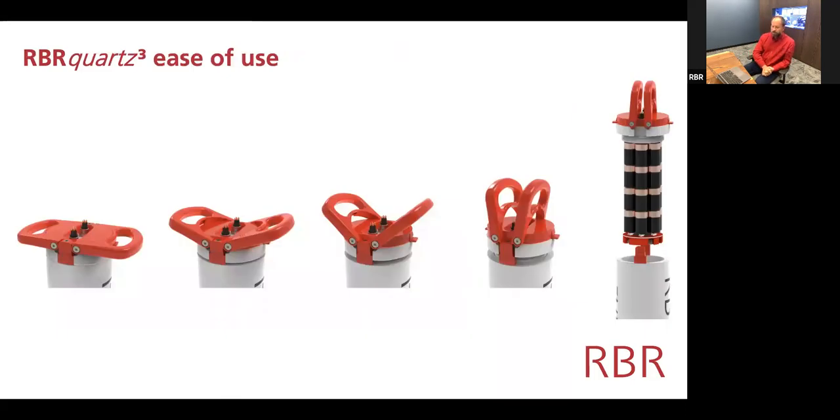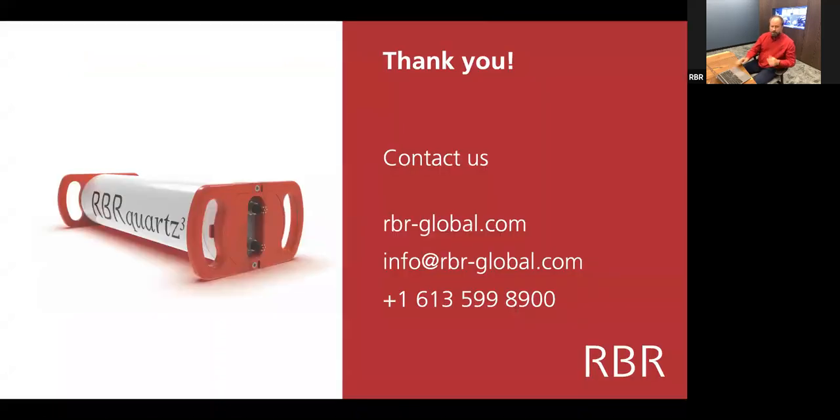We don't ship RBR instruments requiring tools to open them. We want every instrument to be openable using your hands without having forgotten an Allen key — metric or imperial — or particular screwdrivers, or worse, some injection-molded tool customized to the particular instrument. The Quartz³ is designed so that you can pull all the batteries out using folding handles at the top.